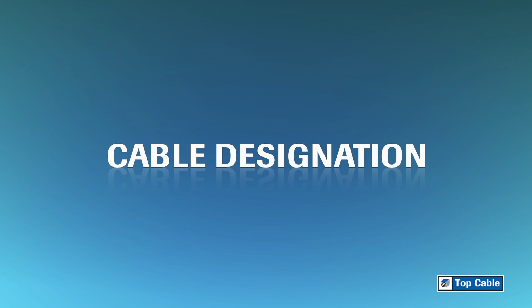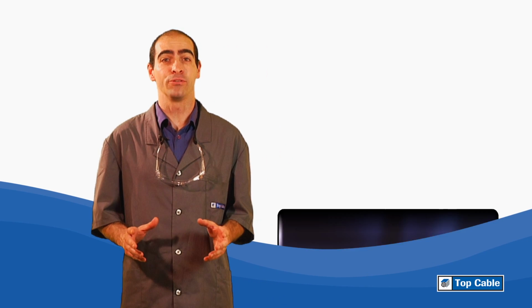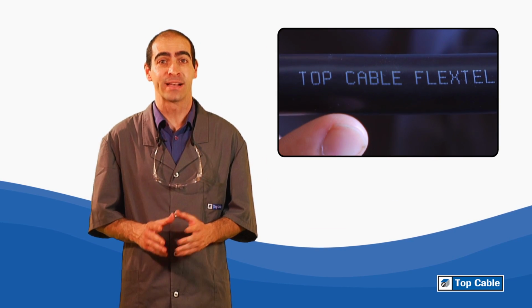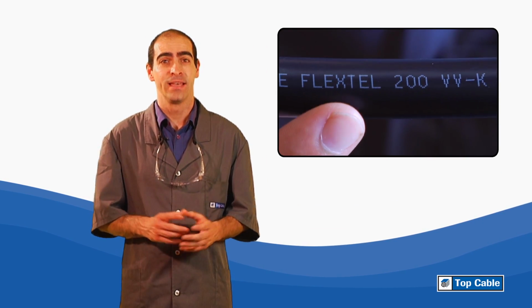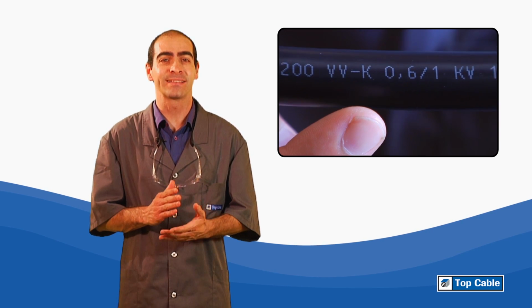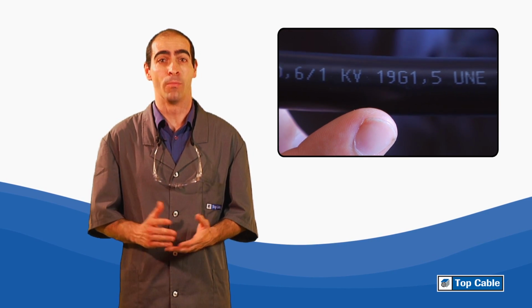In this video blog, we will talk about the cable name and description. Each cable has a name and description code according to the standard. This description is composed by a set of letters and numbers, each one representing a different aspect of the cable's composition. The correct name for the cable and its description allows the buyer or installer to select the right cable and helps to avoid making the wrong selection of cable.